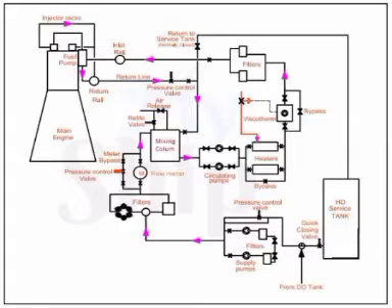If not, the fuel will not move itself because it's not a gravity system. So for you to move the fluid around your system, through your filters, your heater, around the whole entire system up to your fuel injector, something must move it from that service tank around the system to give it that push. So that's where the supply pump comes into play. The supply pump is what transfers the fuel from the service tank through your filters, round up to the mixing column.